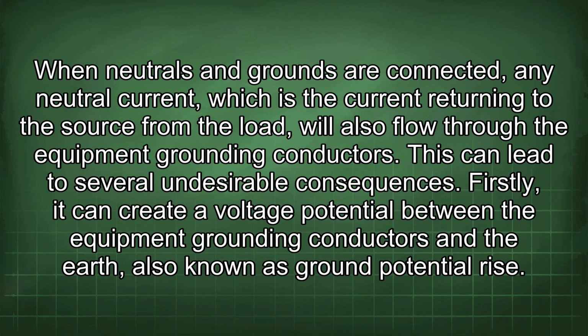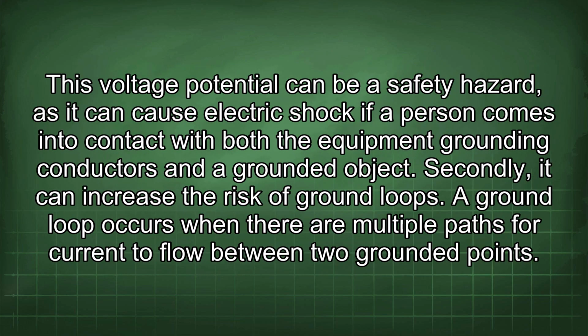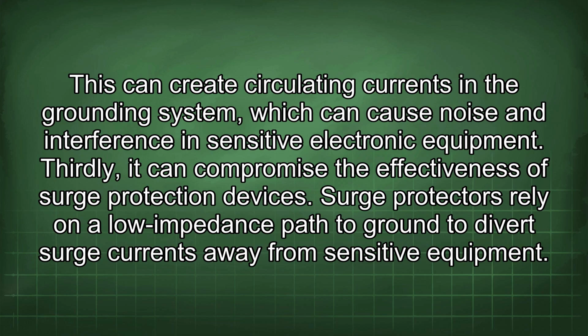Firstly, it can create a voltage potential between the equipment grounding conductors and the earth, also known as ground potential rise. This voltage potential can be a safety hazard, as it can cause electric shock if a person comes into contact with both the equipment grounding conductors and a grounded object. Secondly, it can increase the risk of ground loops. A ground loop occurs when there are multiple paths for current to flow between two grounded points. This can create circulating currents in the grounding system, which can cause noise and interference in sensitive electronic equipment.